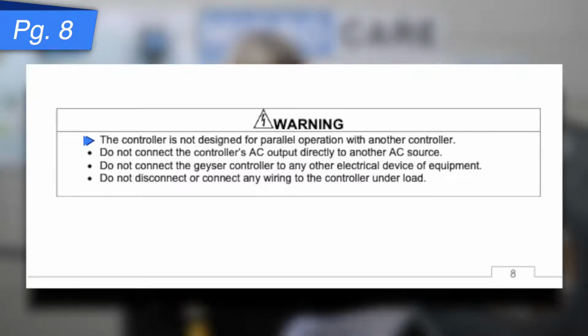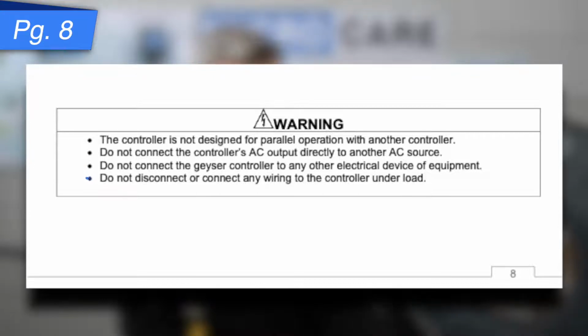This controller, in the warning at the bottom of page 8, reminds you that it's not designed for parallel operation with another controller. It is a 1 geyser controller per geyser solution. Do not connect the controller's AC output directly to another AC supplier. Do not connect the geyser controller to any other electrical device or equipment, and do not disconnect or connect any wiring to the controller when under load.